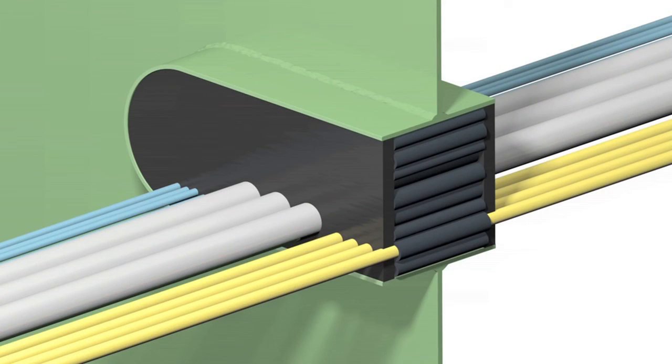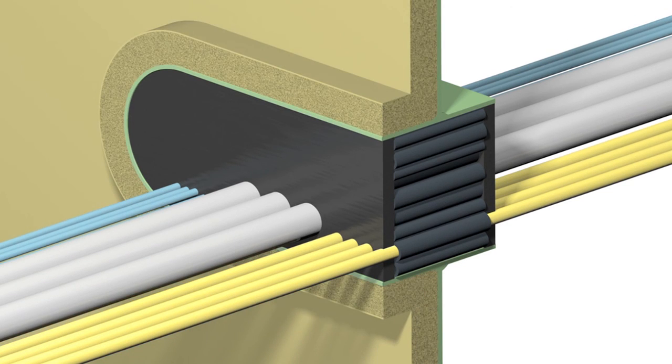For A-class penetrations, which are insulated, the rise multi-cable transit frame needs to be insulated only at the insulated side of the bulkhead or the lower side of the deck. No insulation is required on the cables or the face of the transit.